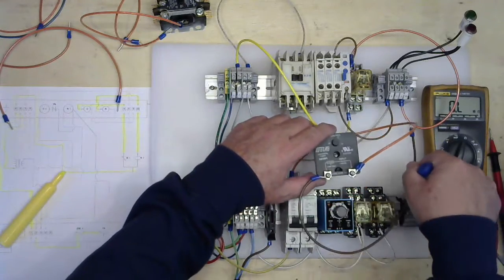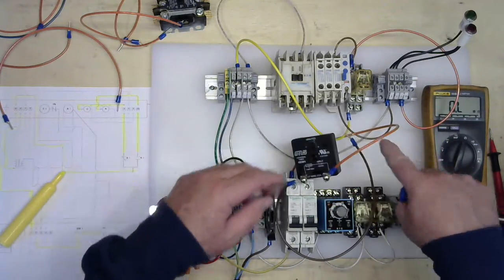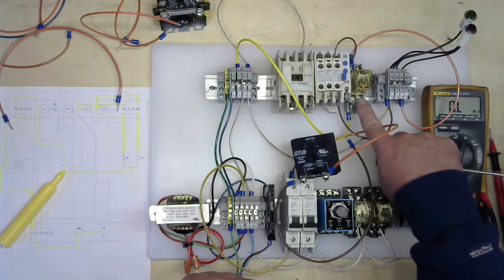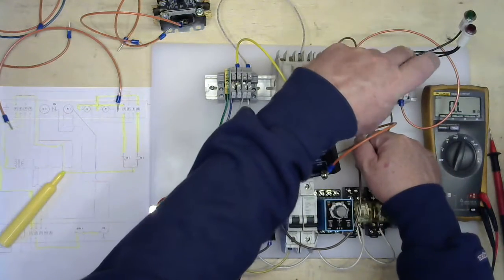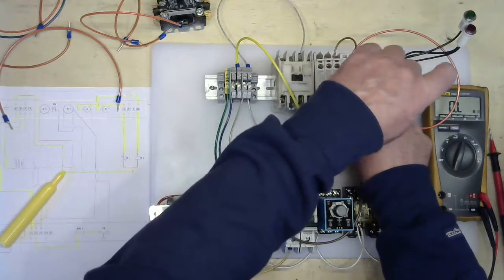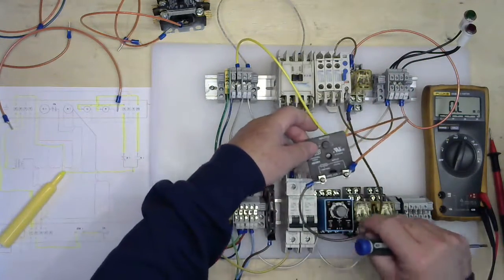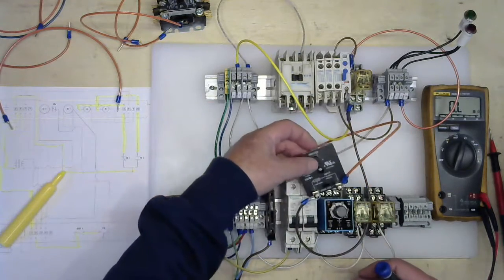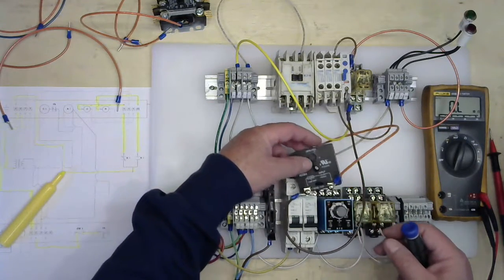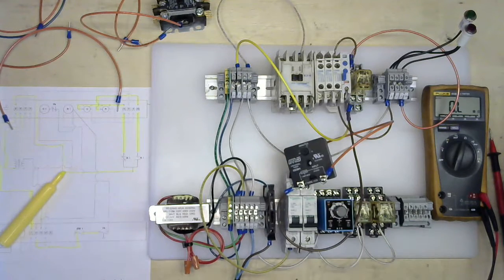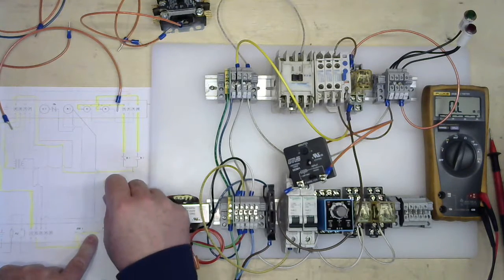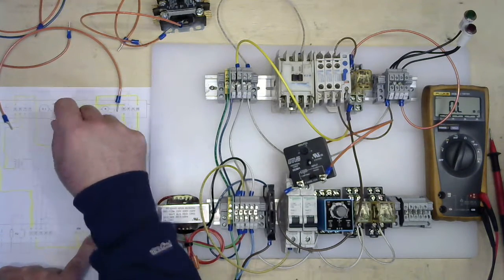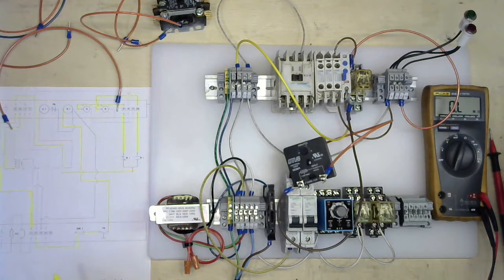Connected on my output here is going to go into the coil of my relay. Now it doesn't matter which side we attach the wire to on the coil, as long as we have a connection. So right now, get that kind of wrapped around there for now. Again, this is for training purposes. It's not something you would do in the field. We have our wire on our time delay input, and our output is going into our relay.